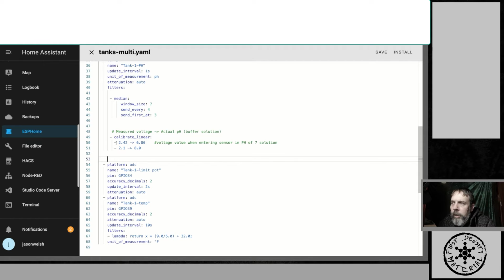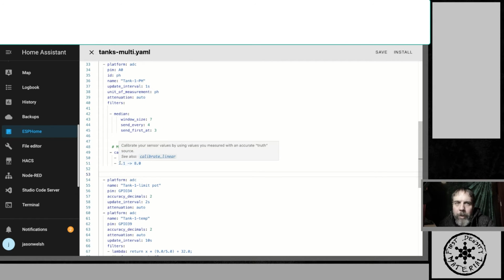So if you see this little tilde, you know that you got bad spacing. All right, so 2.42, it read out to be 6.86. In my case, it was 2.48, and then 2.1 went to 8.0. Okay, and I could do that for the other ones too. So that will calibrate it, and it'll tell it, okay, this is the range it's going to be in, and now when I see a voltage of this, I know it's this, and if I see a voltage of this, it's this. Now it's super smart.